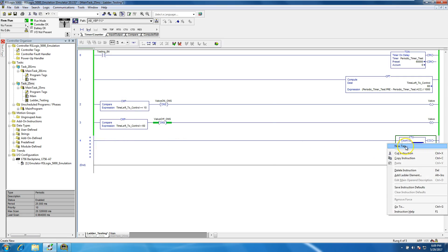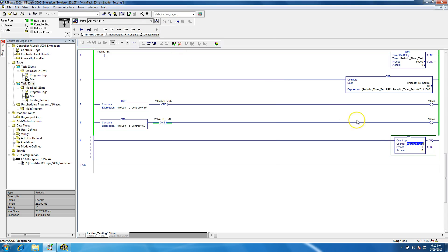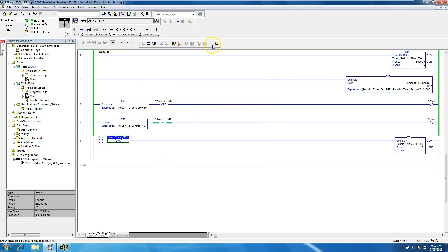Now let's throw in a counter function. We'll call it CTU — 'valve on count' — with a preset of 5. We'll put in the valve-cutting-on condition, add a one-shot again called 'valve count on'. Whenever the valve cuts on it should count one time.